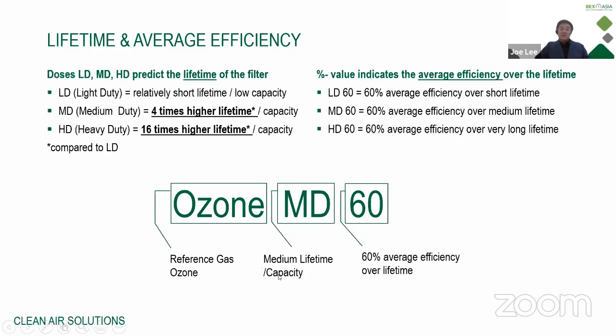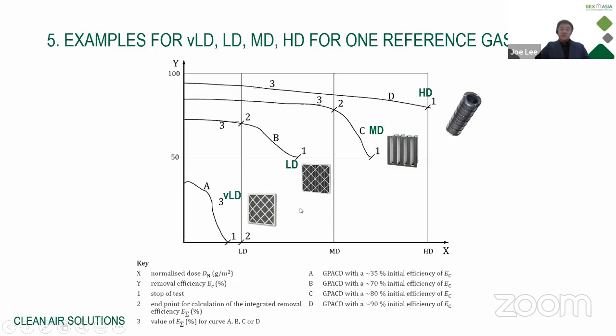And these are the various examples for VLD, LD, MD, and HD. You can see on the right at the top, the HD, which is a cylindrical cartridge. This is a CamCarb CG product from Camfil, where we use loose-fill carbon solutions for heavy usage and heavy duty. And the MD uses compact filters, which have a massive media area, and of course a massive media area will have massive capacity. And for the filter panel, LD and VLD will depend on how many inches this filter is. Is it 2 inches or 4 inches?